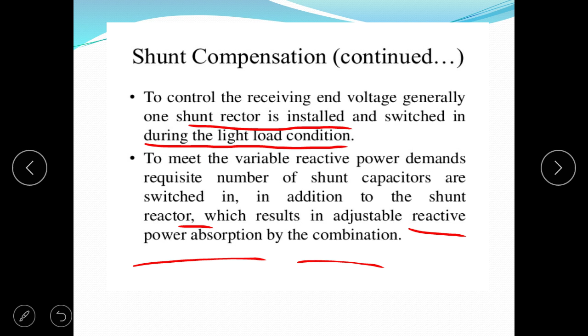To meet the variable reactive power demand, the requisite number of shunt capacitors are switched in addition to shunt reactors, which results in adjustable reactive power absorption by the combination. The advantage of shunt compensation is that we can switch a number of capacitors according to the load requirement or according to the variation in reactive power. But this facility is not available in series compensation.